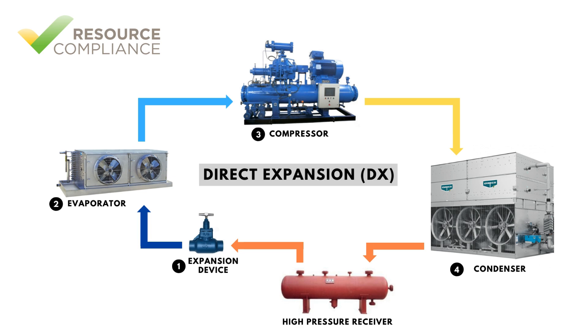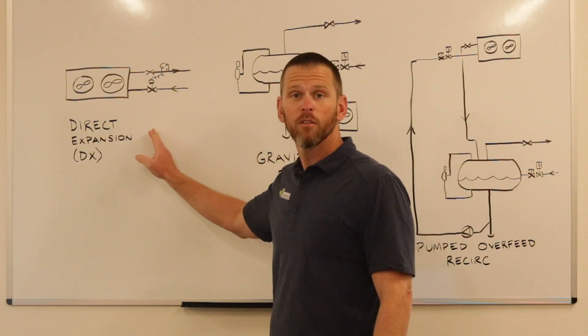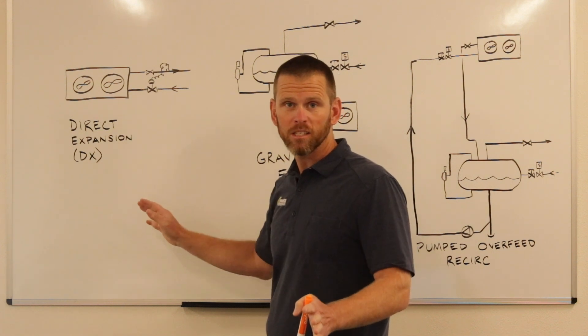The vapor that forms is called flash gas and is unwanted, since the vapor must travel through the evaporator but has no potential to absorb latent heat. The beauty of the DX system, however, remains its simplicity.